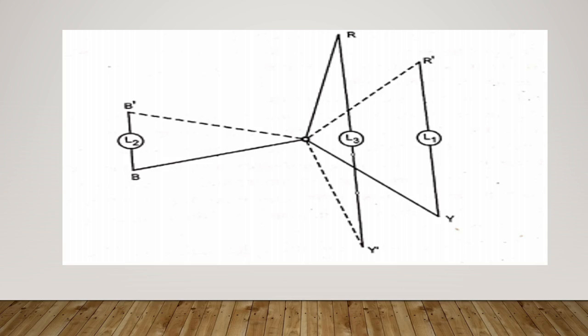So the paralleling switch will be closed when the changes in light are very slow, and at the instant the lamp L2 is connected directly across, one phase is dark. In case of high voltage generators, which is the usual case, direct connection of lamps is not practical. In such cases, lamps may be connected through potential transformers.